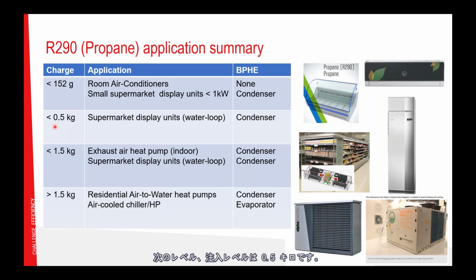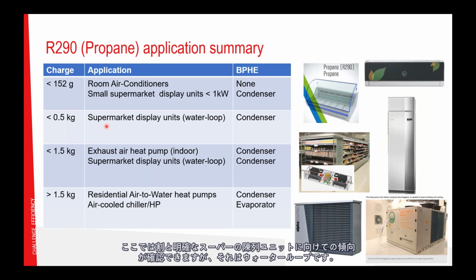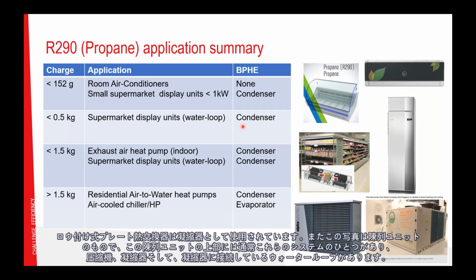The next charge level is 0.5 kilo. And here we see a quite clear trend towards supermarket display units, and that is water loops. Brazed plate heat exchangers are used as condensers. And in this picture, you can see a display unit. On the top of this display unit, there is typically one of these systems where you have a compressor and a dual brazed condenser. And then you have a water loop feeding the condenser.